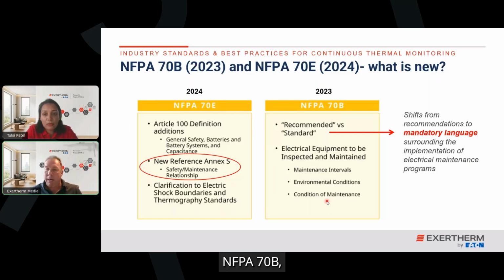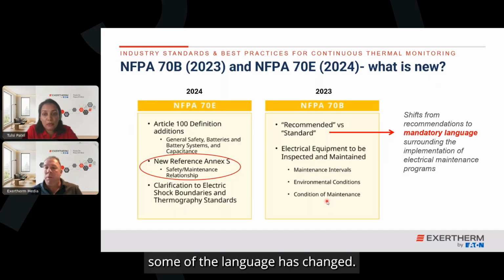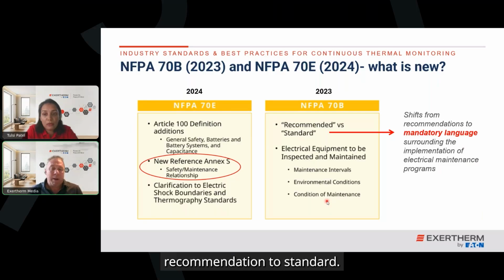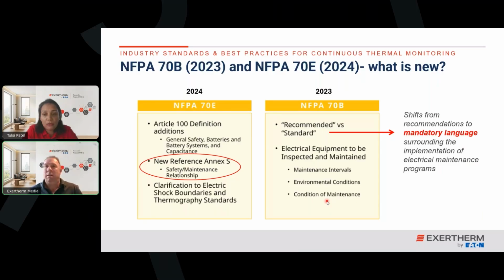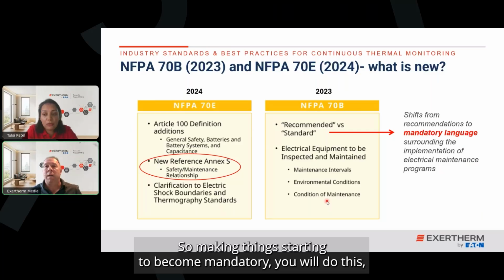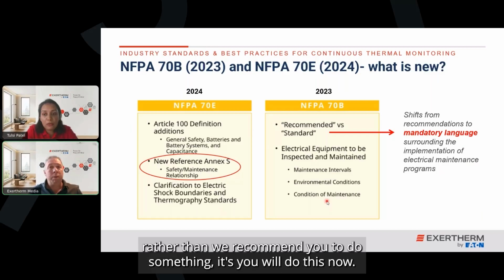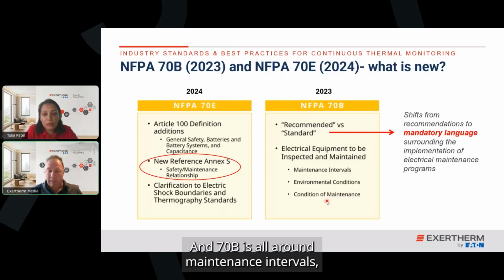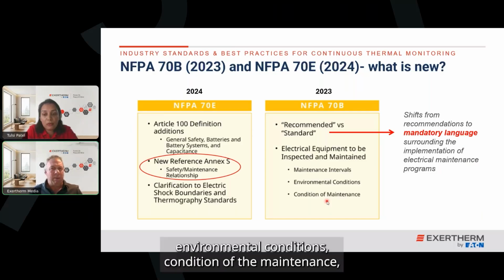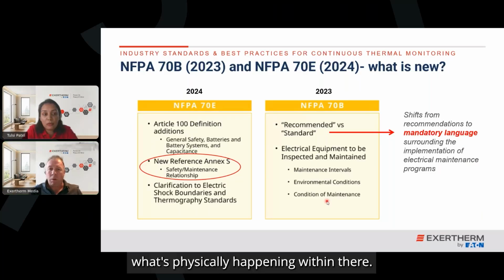NFPA 70B, some of the language has changed. There's been a shift from the word recommendation to standard. So things are starting to become mandatory. Rather than we recommend you do something, it's you will do this now. 70B is all around maintenance intervals, environmental conditions, condition of the maintenance, what's physically happening within there.